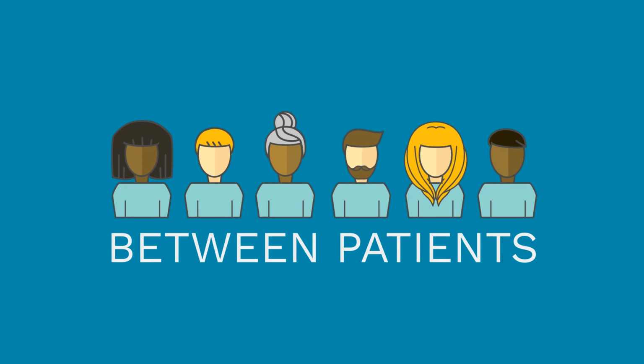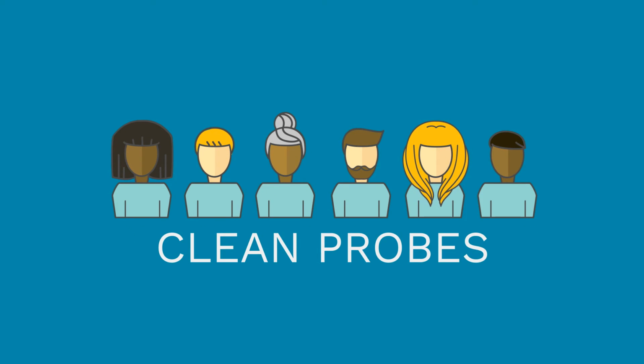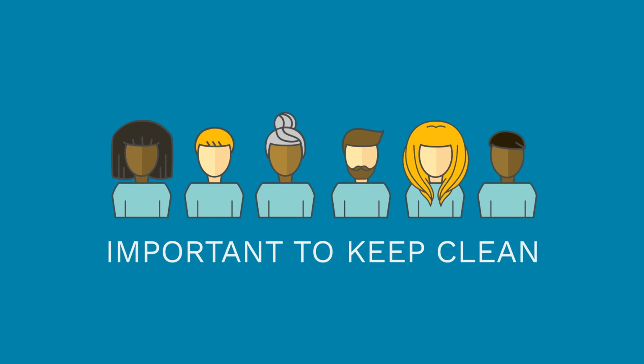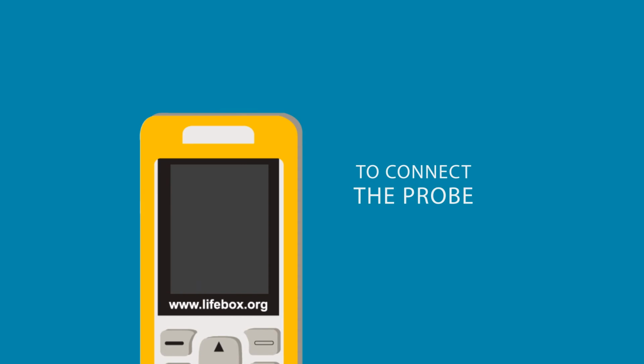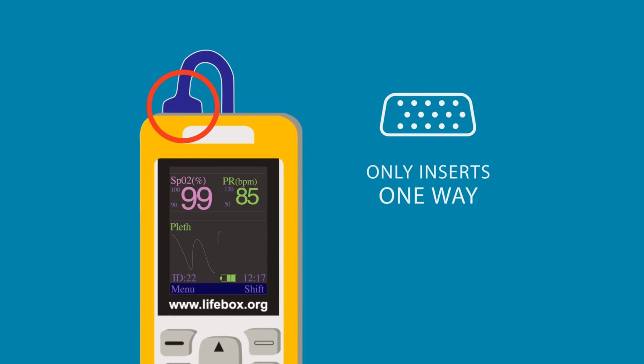Between patients, you must clean the probes gently with a damp cloth or alcohol swab. It's important to keep the LED and photodetector clean. To connect the probe to the oximeter, plug the base of the probe into the top of the oximeter here. Note that the probe only inserts one way. The pins are arranged in a sloping shape.